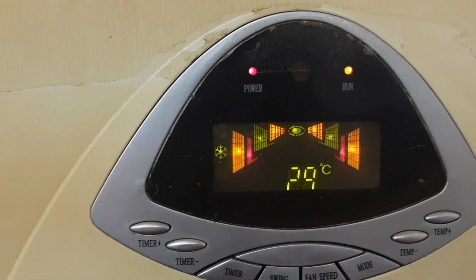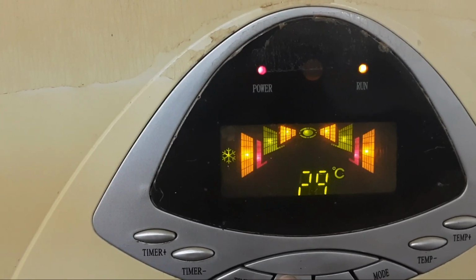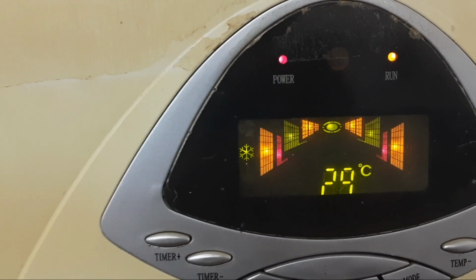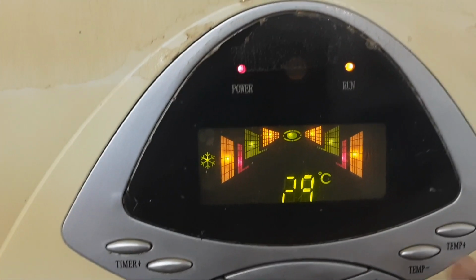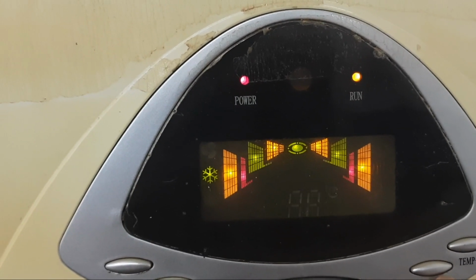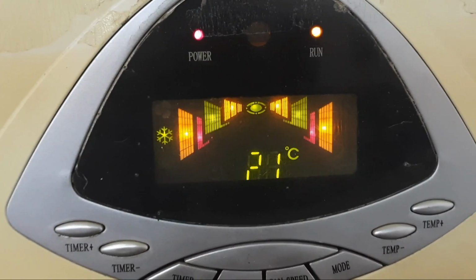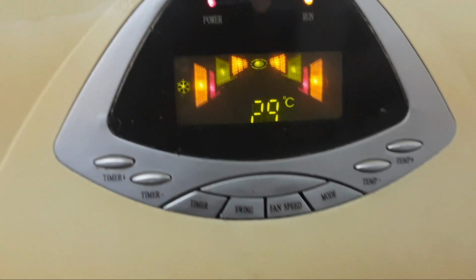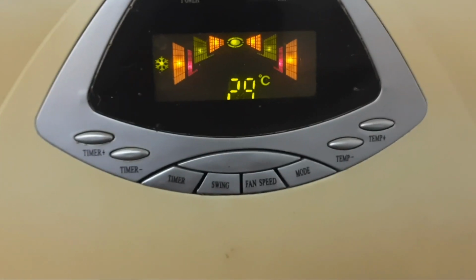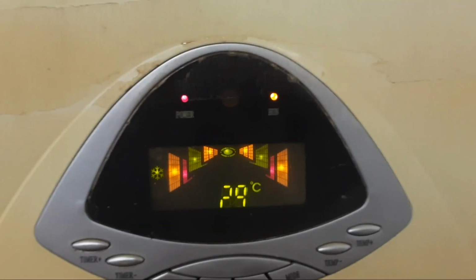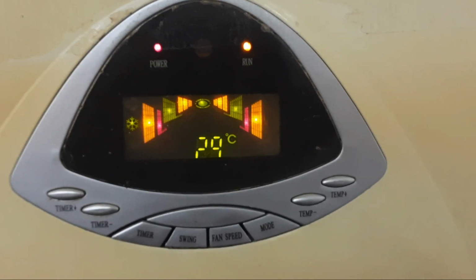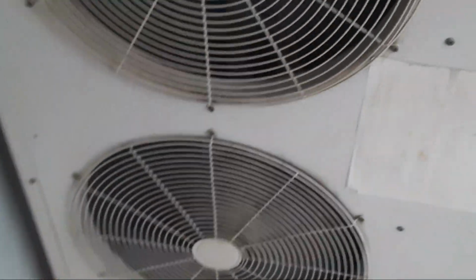So it's not a big deal to check your units by yourself. If any issue comes in your unit, you first check your wiring. Maybe your wiring has issues, maybe some cable is cut, maybe because of short circuits. And this was amazingly cut by a rat, because I found too much dirt inside the unit, which was brought by the rat. After fixing that issue, I closed the unit properly, so as not to welcome the rat back again.